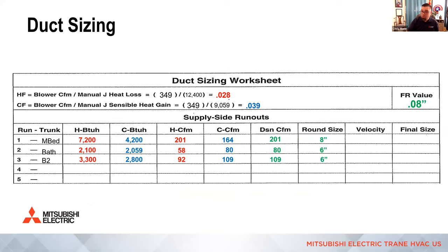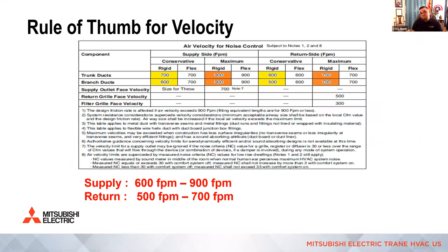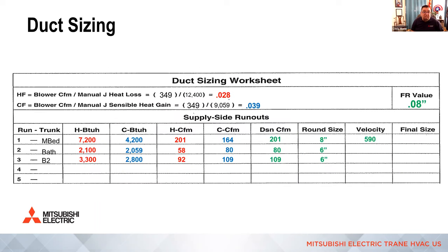So when we kick back to that worksheet, what we're going to do is line up the duct calculator directly to the first round size. In this example, it's 8 inches. And that 8-inch round duct, when we look at volume of air of 201, you can see it falls right at about 590 feet per minute. Now, if you remember on the previous screen, I'm just going to kick back a screen here. The minimum on a supply should be 600. So unless this is a really short run, we don't want to stick with an 8-inch. We want to make sure we downsize to 7-inch.